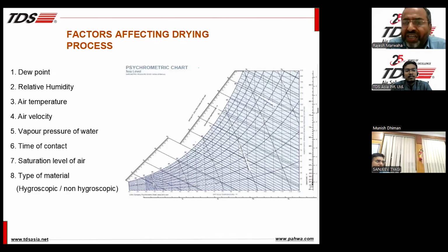This is basically the psychrometric chart. It gives you the wet bulb reading. When we measure the wet bulb and dry bulb on the psychrometric chart from readings taken in the room, you find the grains, meaning the moisture level in the room, how much moisture is present. Because if there's more moisture, it's going to cause more damage to the equipment.